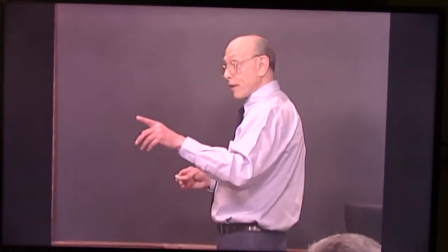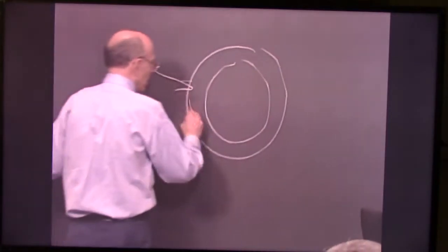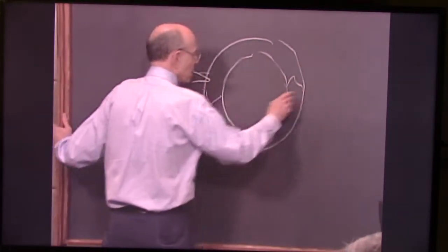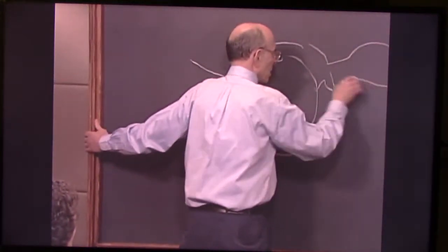That's right. So if you've got the reservoir bag on, even though you've got a high flow that you leave on all weekend, no problem. And that's because, here's our circuit. Here's the gas flow coming in. And there are one-way valves. And here's our reservoir bag over here.